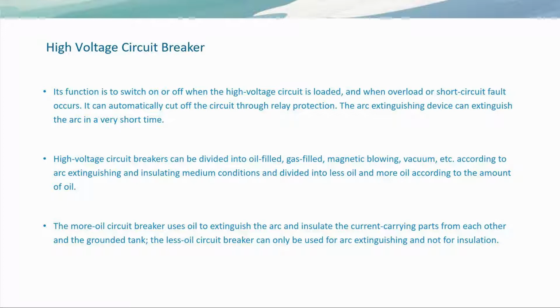There are many types of high-voltage circuit breakers, which can be divided into oil-filled, gas-filled, magnetic blowing, vacuum, etc., according to arc extinguishing and insulating medium conditions, and divided into less oil and more oil according to the amount of oil. The more oil circuit breaker uses oil to extinguish the arc and insulate the current-carrying parts from each other and the grounded tank. The less oil circuit breaker can only be used for arc extinguishing and not for insulation.